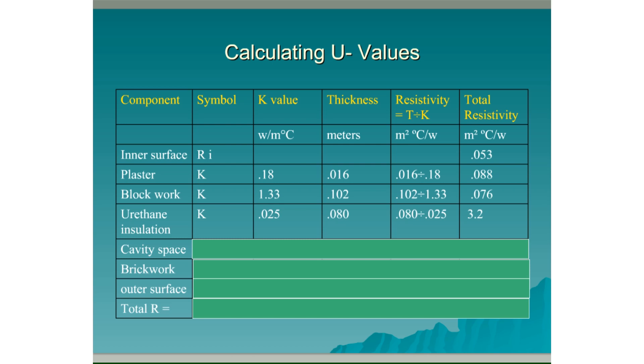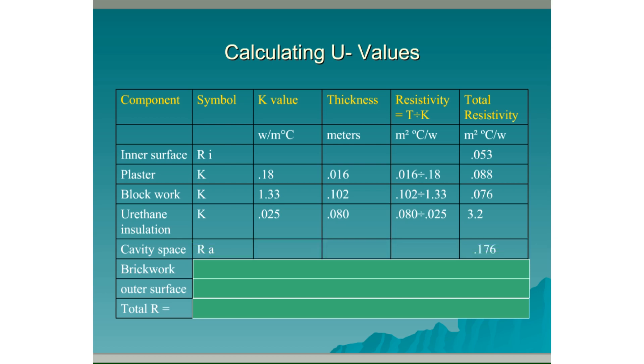The urethane insulation has K value 0.025 — much lower than the block work. The lower the K value, the more resistance it has to heat passing through it. The block work's K value of 1.33 allows heat to pass fairly quickly, whereas the insulation's K value of 0.025 means heat passes through it much more slowly. The insulation thickness is 0.080 m (80 mm): divide thickness by K value to get the total resistivity. The cavity space (symbol RA, air resistance) has a total resistivity of 0.176.